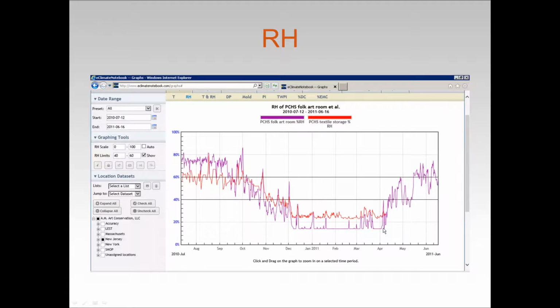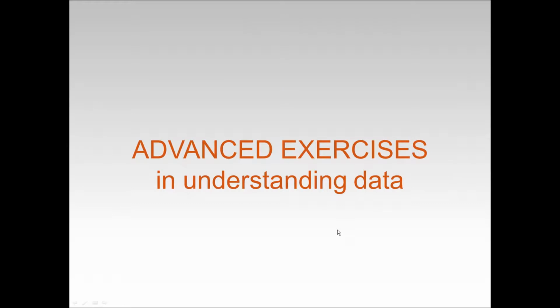It bottomed out at 15%. That data logger was not actually capable of registering RH levels under 15%. So in fact, their data was worse than what they thought they were looking at. So again, if you ever see completely flat lines or completely straight lines like in that earlier graph, let me know, because there's something funky going on.